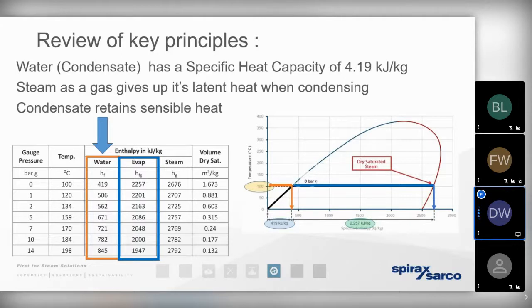We've mentioned in previous presentations that sensible heat, that condensate, doesn't have any heat that can be considered useful by the process. So to a certain extent, it can be considered as a byproduct. But what you'll remember from previous presentations is there's still a considerable amount of heat energy contained within that condensate. We just need to be more creative about how we find a way to utilize that energy. And this will become apparent as we go through the coming slides.